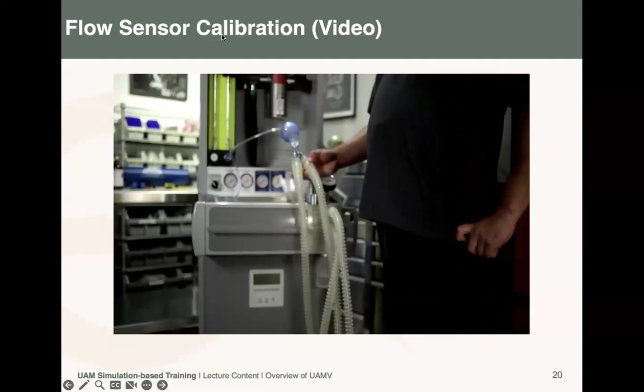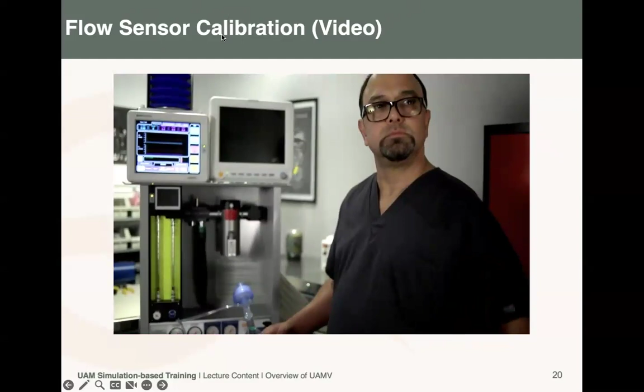Airway pressures, and tidal volume. The patient flow sensor requires calibration when being used for the first time, periodically every few weeks, if damage is suspected, after cleaning, and if the set volumes and pressures differ from the measurements displayed on the screen. These are the items you will need. Red calibration connector. Calibration procedure.